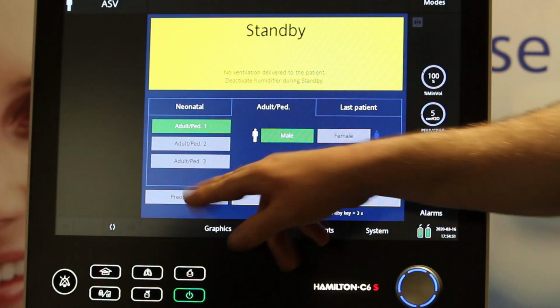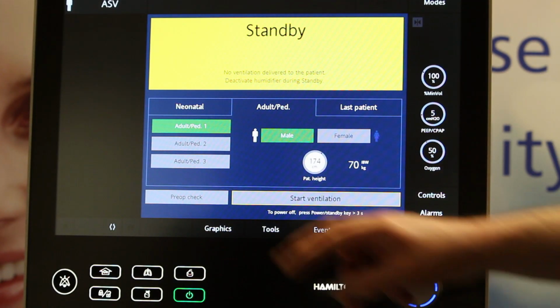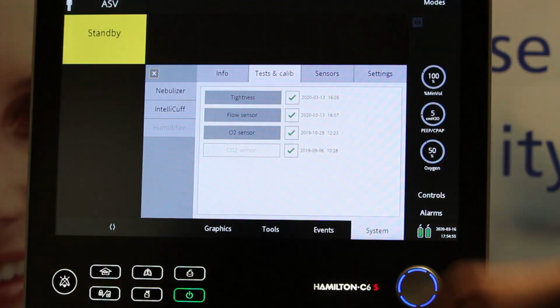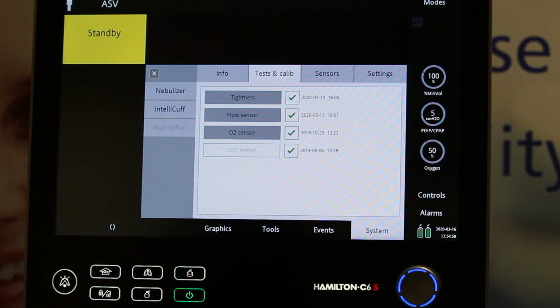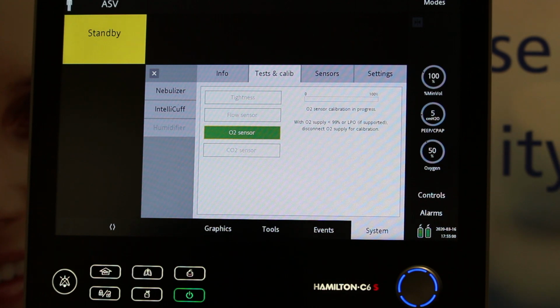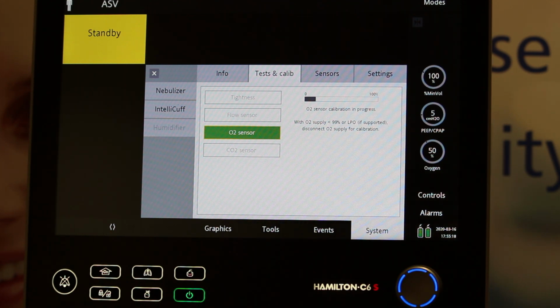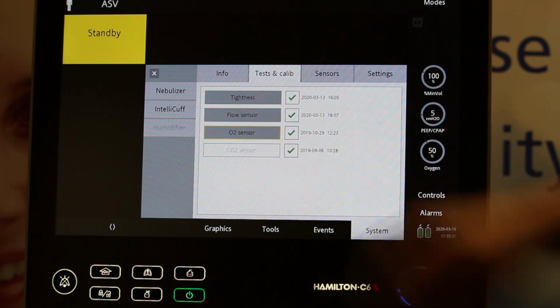So here on the bottom left hand of the screen you'll see the pre-op check, and that's where I'm going to test the circuit. When I hit pre-op check, you see there's 2 tests that must be done every time on the circuit, and also there's an O2 sensor test. You only need to do the O2 sensor test when you're prompted by the ventilator. You'll be prompted with a little message to tell you to test the O2 sensor. If you get the message, just press the O2 sensor button and it will calibrate the O2 sensor itself in the background. That takes 2 minutes, but you don't need to do it every time. You just need to do it when you're prompted by the ventilator.